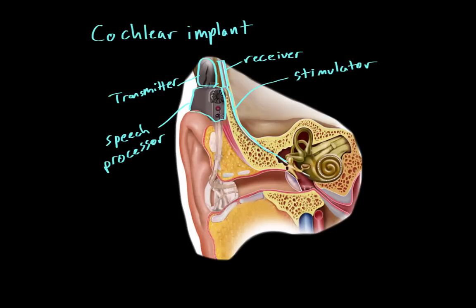The speech processor gets information through a small opening, which is the microphone. As sound waves come in, they hit the microphone, which converts them into an electrical impulse. That impulse is sent to the transmitter, which is outside the individual's skull. The transmitter then sends the information to the receiver, which is implanted inside the patient's skull. The receiver sends the information through the stimulator into the cochlea, which converts the electrical impulse into a neural impulse that travels down the auditory nerve to the brain to be processed.